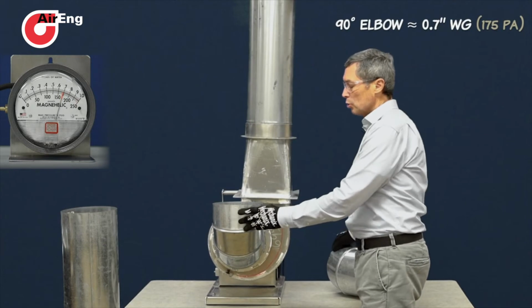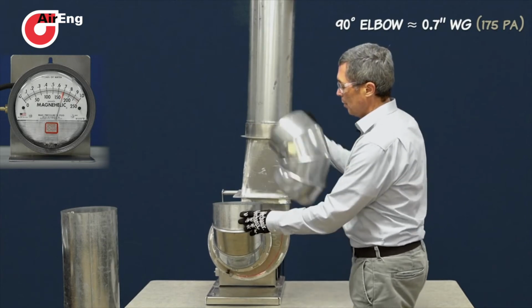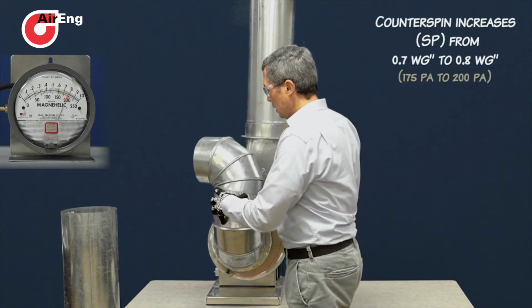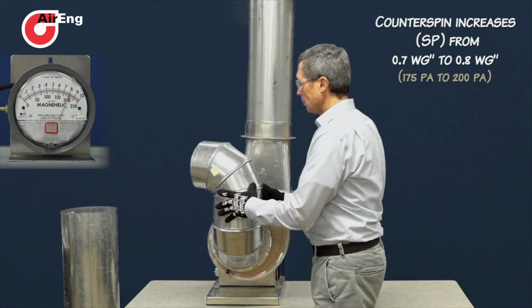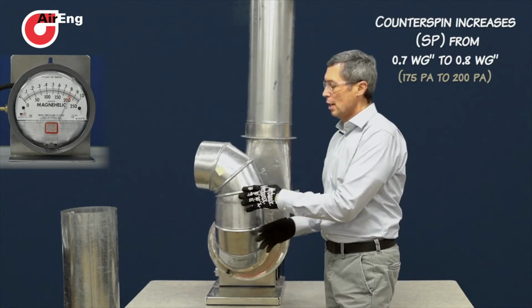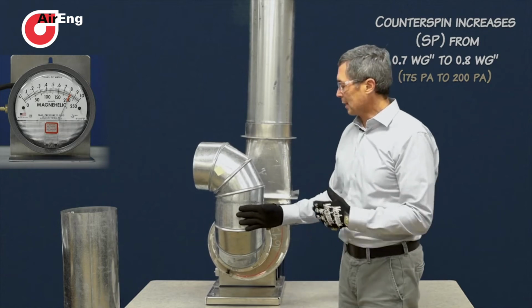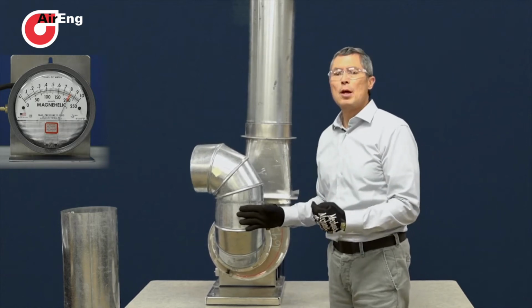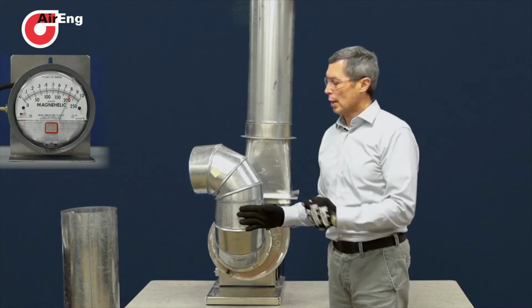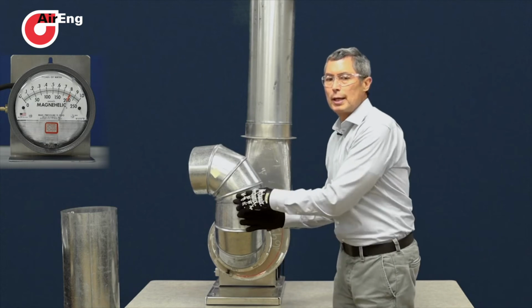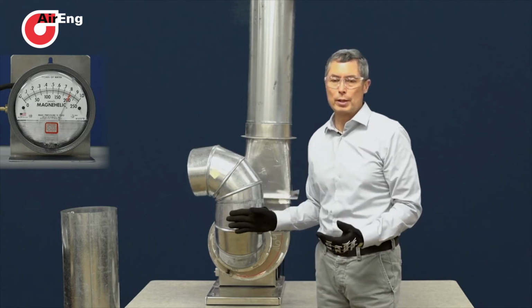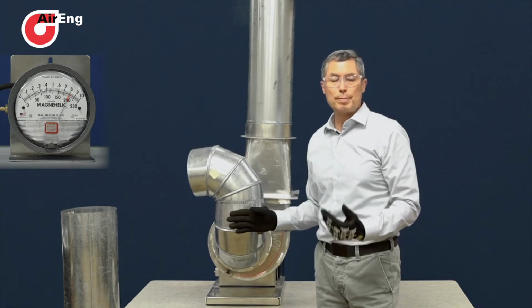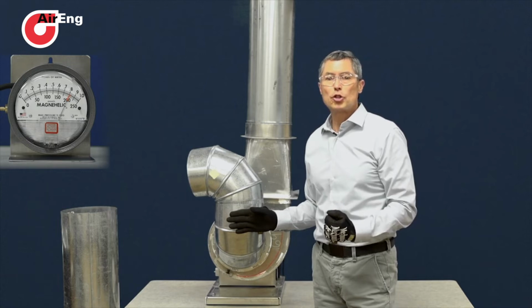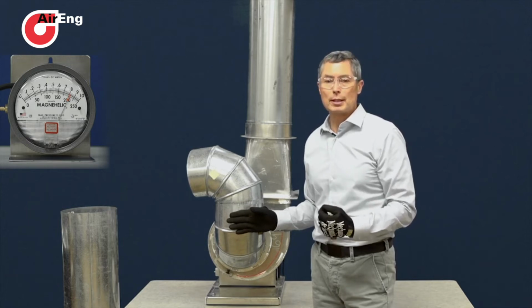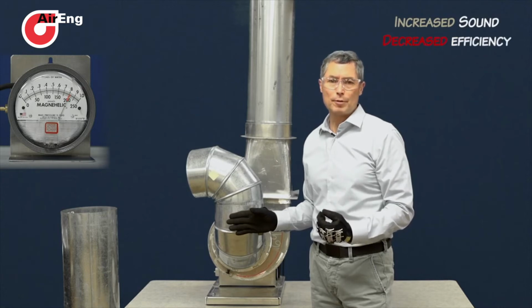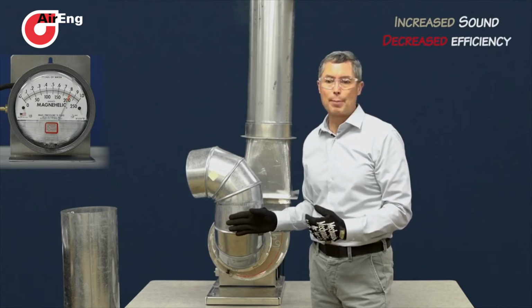Like our earlier videos, putting a 90-degree elbow decreases fan performance, and now we're going to counterspin the air and see what changes. Notice a couple things. When we look at the magnehelic gauge, performance actually increased. So a lot of times people think, hey, this actually makes the fan run better. Why don't we do this more often? You also notice that sound increased as well. We're counterspinning the air as it enters the fan. So it's like an airplane wing taking off into a strong headwind. While we've increased lift, or the ability of that wheel to move the air, we've also created turbulence, and that turbulence results in increased sound as well as decreased fan efficiency. So the fan actually consumes more energy during operation.